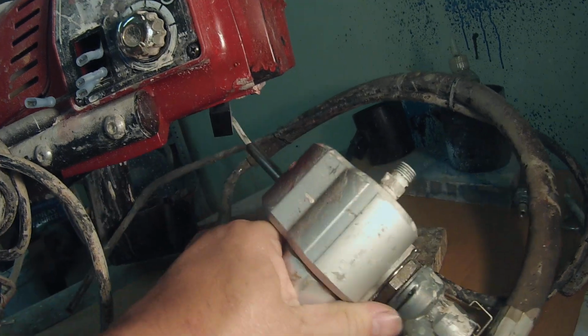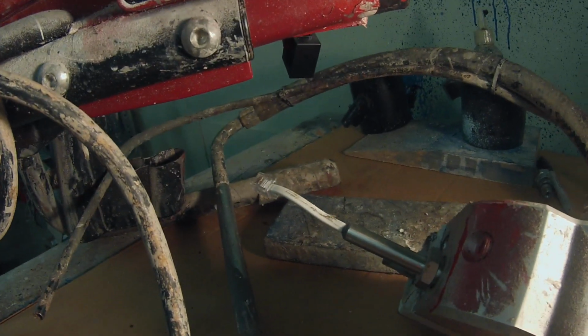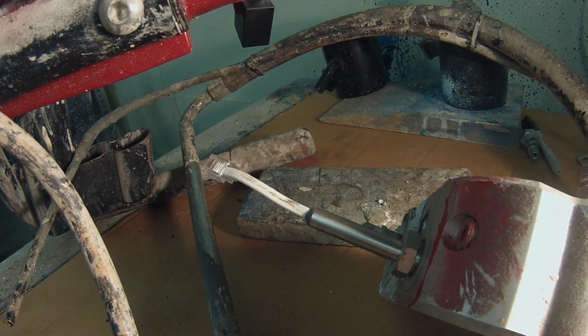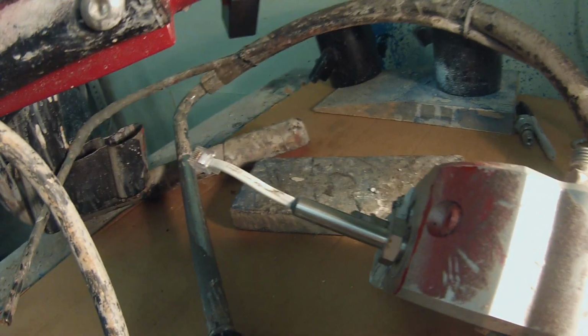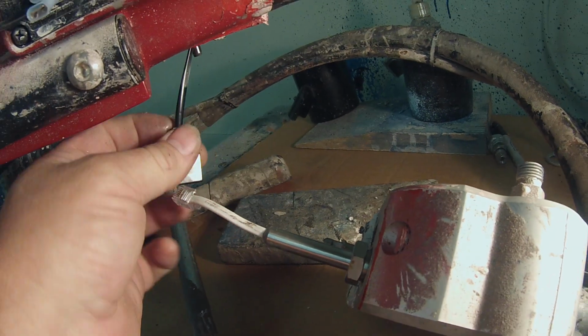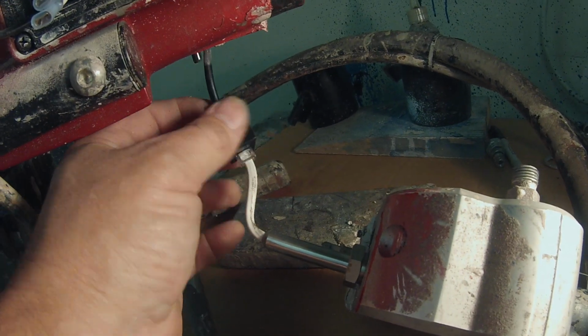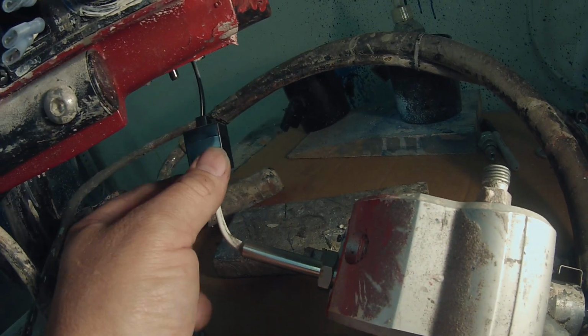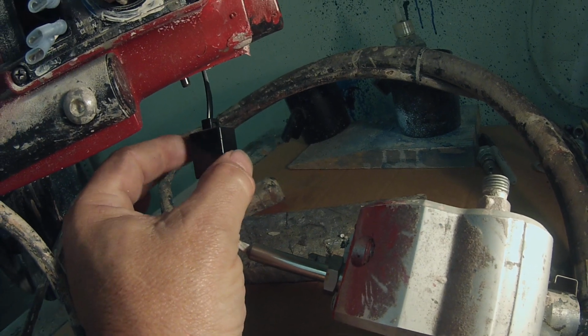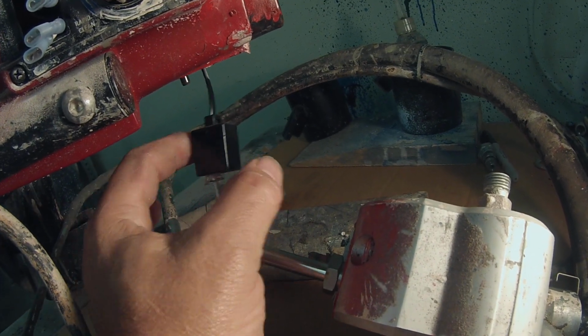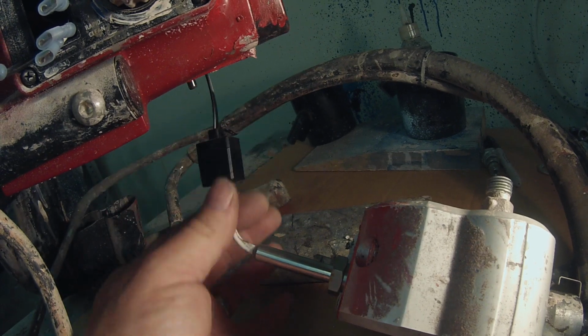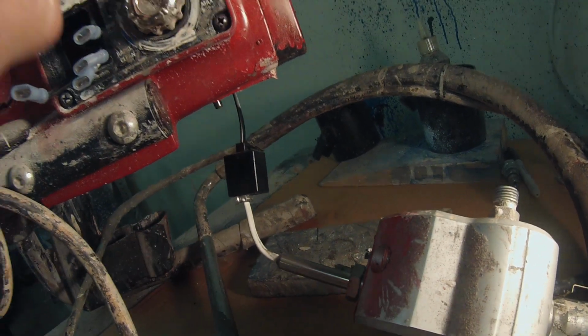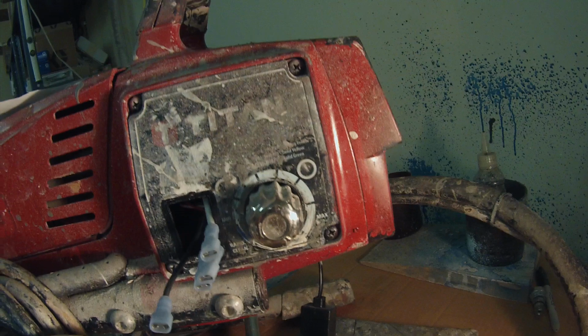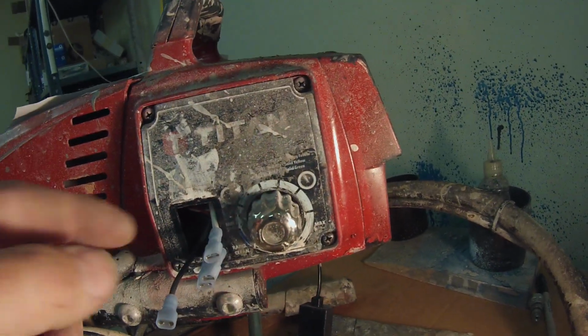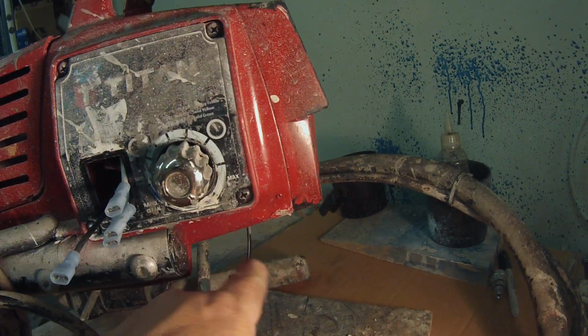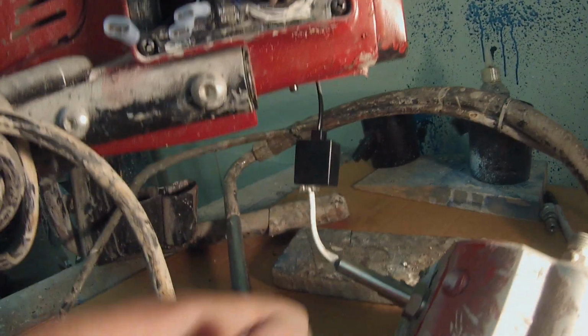Once you get it down, your transducer is right there. There's your transducer. Now it's going to come down, and you may have to stick your finger up inside of the hole, up in here, to knock the jumper loose, because it'll catch on the corners. Knock it loose, and you'll be able to pull it down. If you can't, take the screws out of the cover plate here, pull this off, and you can push this down through the hole inside, and that'll expose it.